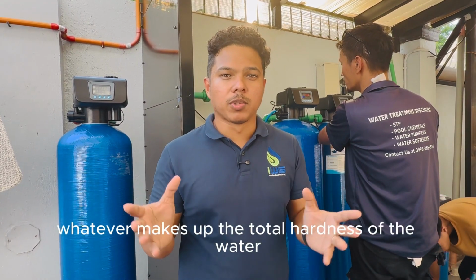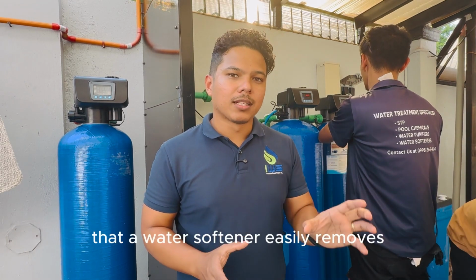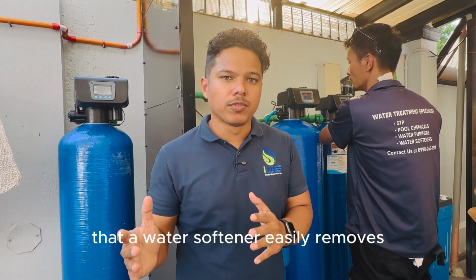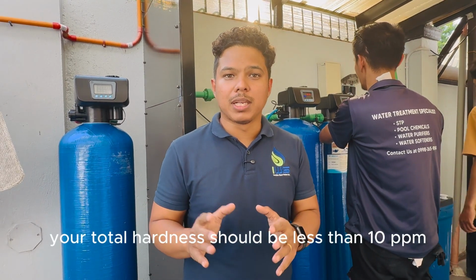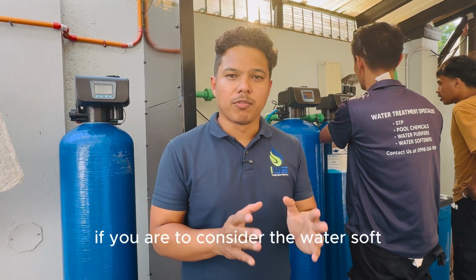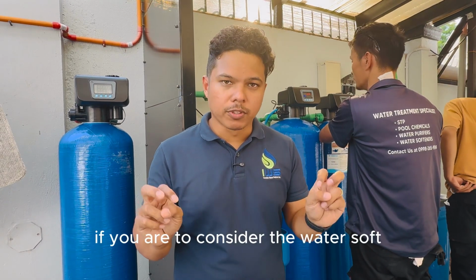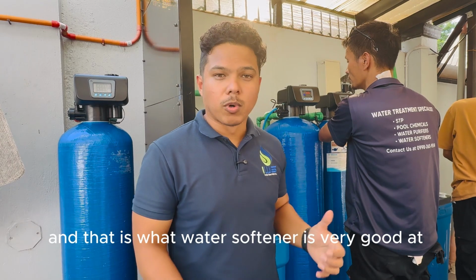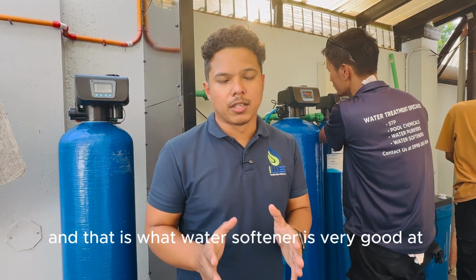Whatever makes up the total hardness of the water, a water softener easily removes, and your total hardness should be less than 10 ppm if you are to consider the water soft. And that is what a water softener is very good at doing.